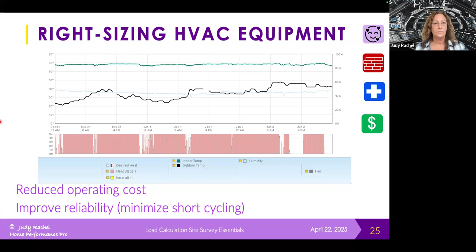The direct quote from the Manual J load calculation is that using this smallest defensible load approach to equipment sizing is going to optimize not only the system's performance, but it's also going to maximize your customer satisfaction. So that smallest defensible load approach is that we're doing an accurate load calculation. We're not padding it in any way. And then we're looking at equipment that best matches the loads.